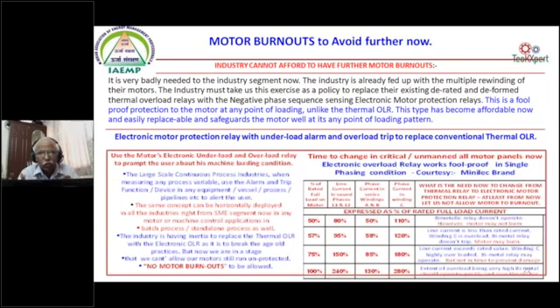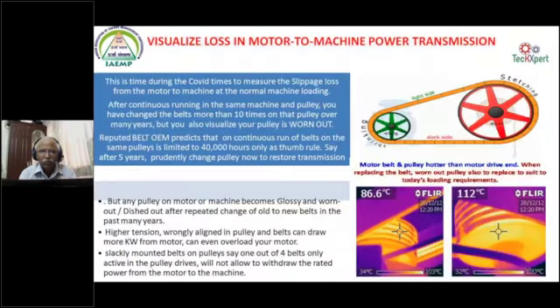It can also be used as a parameter for the given system. You can set your underload to catch inefficient loading. Let us say a motor is running between 60 and 80%. 80 is your higher loading, where it can trip or give an alarm. And if it goes below 50%, it can give an alarm for lower loading. The equipment has to be run efficiently at an efficient loading, and that can be checked.